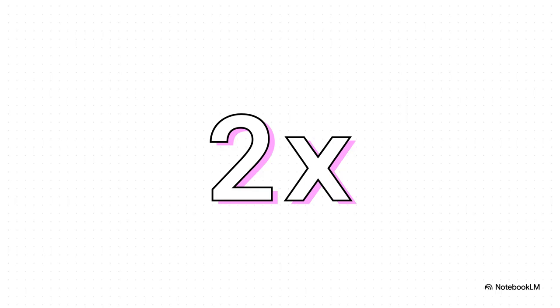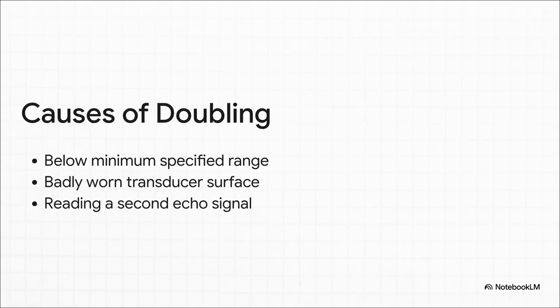You're testing a corroded pipe, you read that it has plenty of thick steel left, but in reality, it's dangerously thin and on the verge of bursting. Scary stuff, right? So why in the world does this happen? Well, it primarily occurs if you're testing a material that falls below the minimum specified range of your transducer, or if you're using a badly worn probe with a damaged front surface. Essentially, the sound wave bounces back and forth multiple times, creating a second echo, and the machine gets totally confused, just adding those trips together.